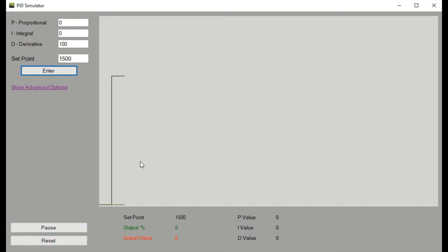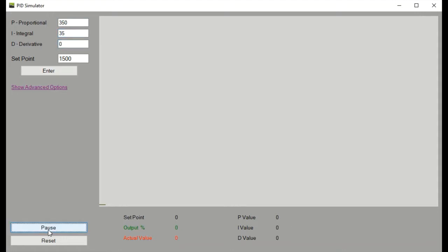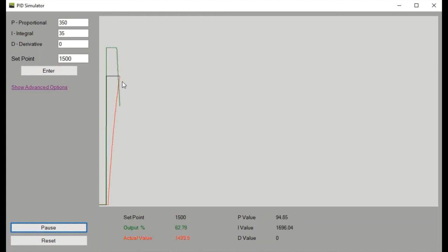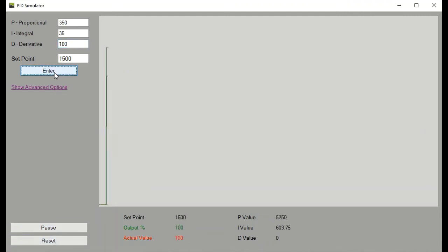Looking at the derivative in the simulator, by itself it will have no effect on the output of the controller. Notice we have a set point of 1500, but because there's no ramp rate of the actual value, the derivative has no effect. But if we put in the values we had before — P of 350, I of 35, and D of 0 — while this is a good PI controller, notice there is some slight overshoot over the set point. That's where the derivative comes into play. Giving a derivative of 100 and resetting the controller — watch how the derivative pulls back on the output to prevent the actual value from overshooting the set point.